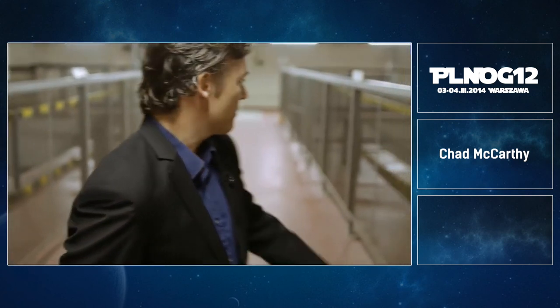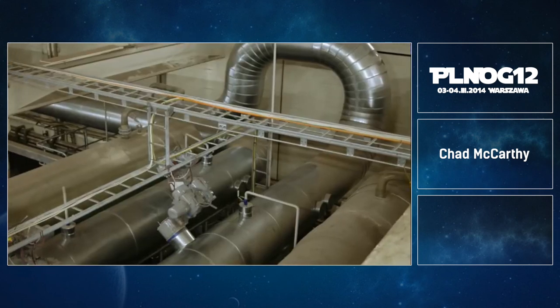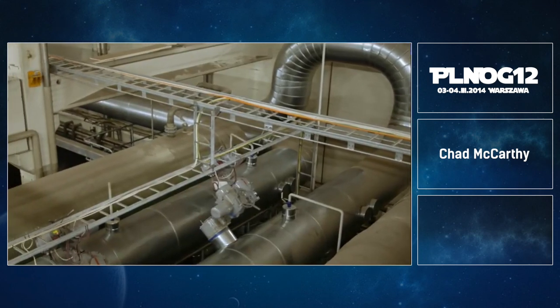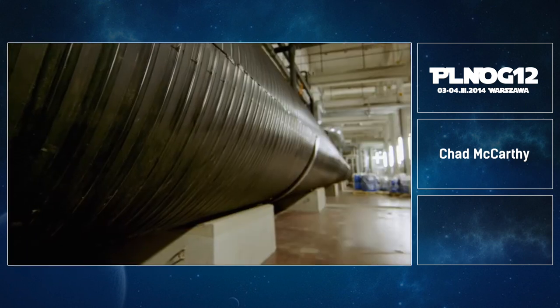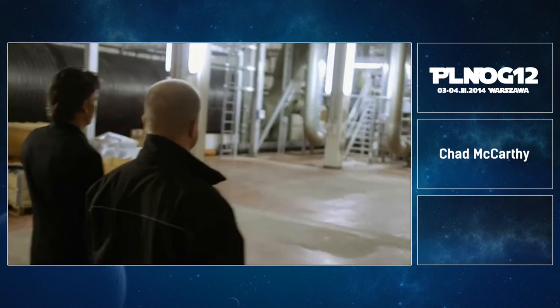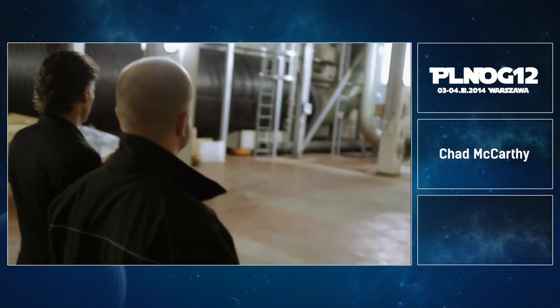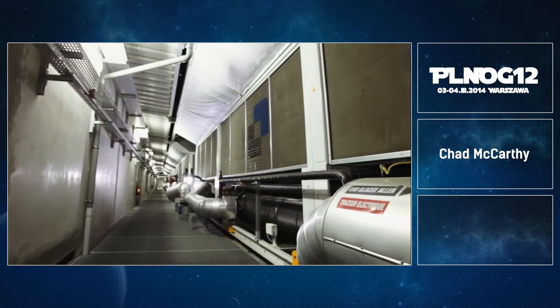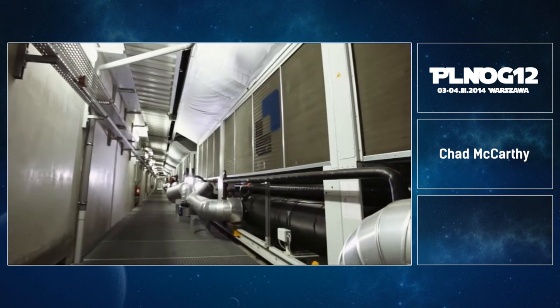So on the left-hand side, we have some very large pumps which take the seawater. They then go through extremely large heat exchangers on the right-hand side, and then the seawater flows back to the ocean via gravity via this enormous pipe on my right-hand side. We are reducing the CO2 footprint of the data center because we're not consuming electrical energy to run compressors and using refrigerants to form cooling. It's an example of free cooling, which is a little bit outside the norm.